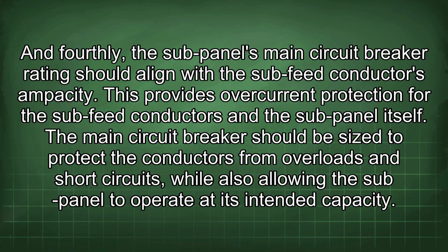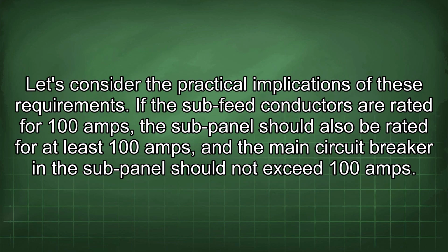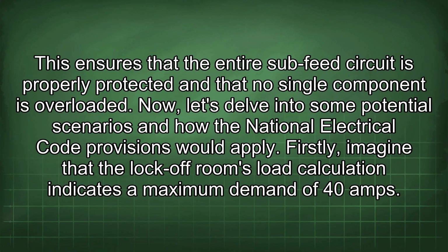The main circuit breaker should be sized to protect the conductors from overloads and short circuits, while also allowing the sub-panel to operate at its intended capacity. Let's consider the practical implications of these requirements. If the sub-feed conductors are rated for 100 amps, the sub-panel should also be rated for at least 100 amps, and the main circuit breaker in the sub-panel should not exceed 100 amps. This ensures that the entire sub-feed circuit is properly protected and that no single component is overloaded.